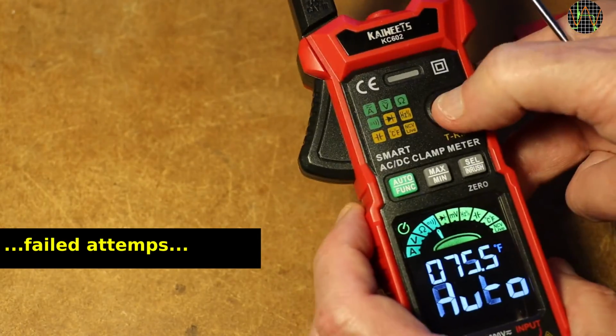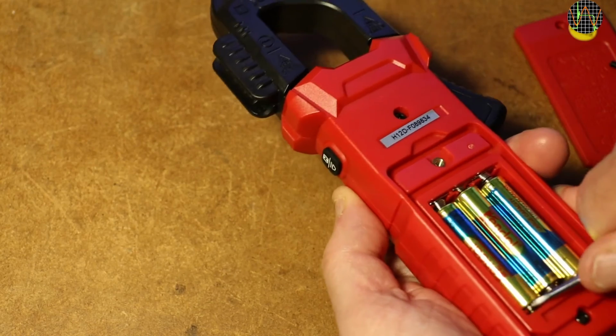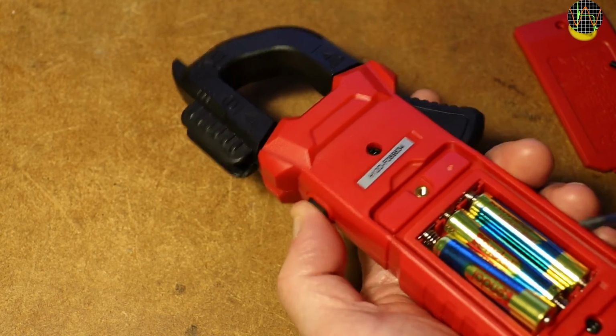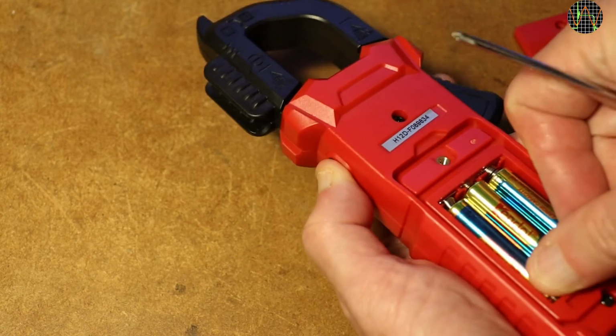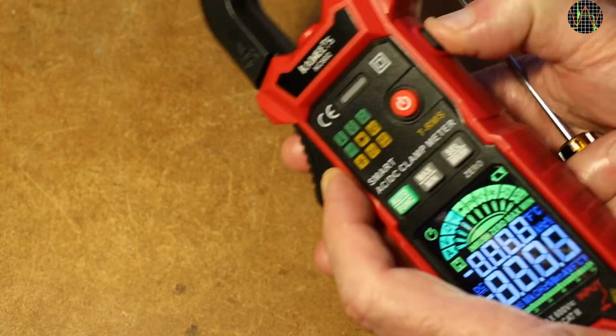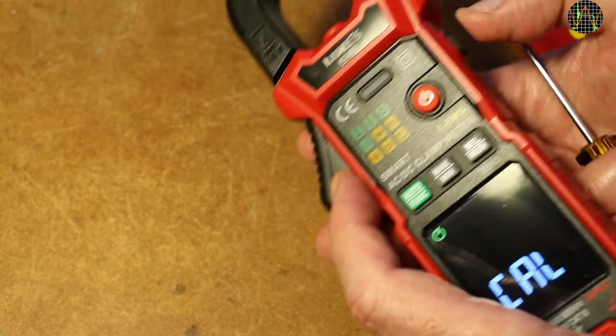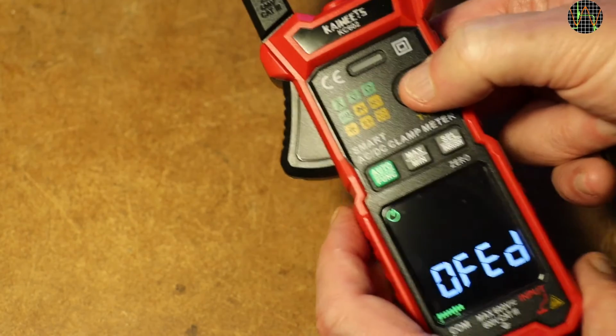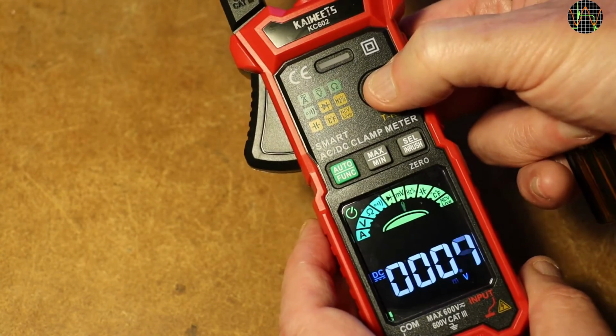By the way, you should not have the leads connected to the meter during this process. You take a battery out, and then, before inserting it back, press hold and keep it pressed. Then, while the meter is still showing all segments on the display, let go of hold and start pressing it with short presses repeatedly. If your timing is right and the stars align, you now get a screen showing briefly U1.00, which is probably the firmware version or something like that. I think you are now in a genuine calibration menu.